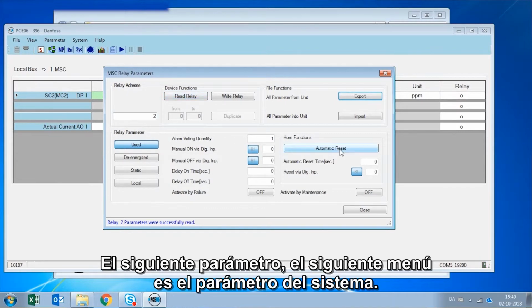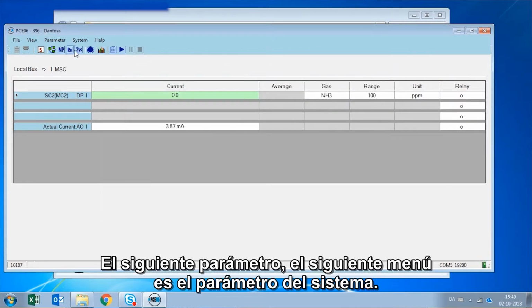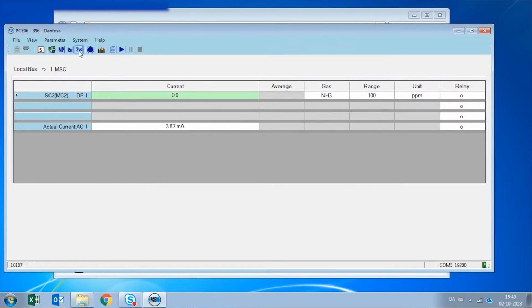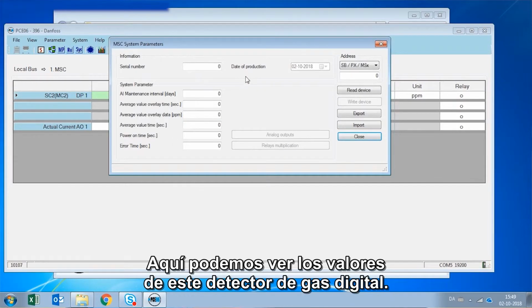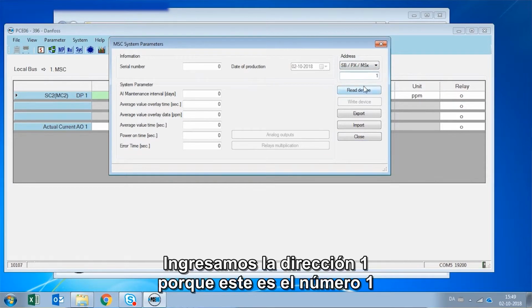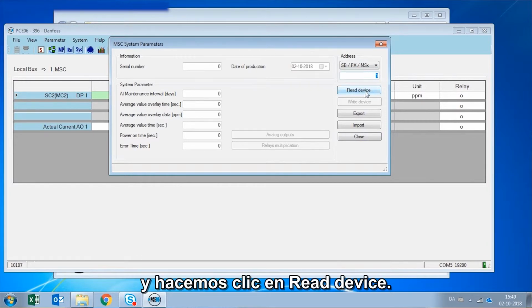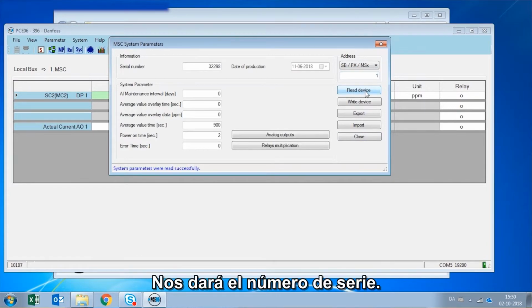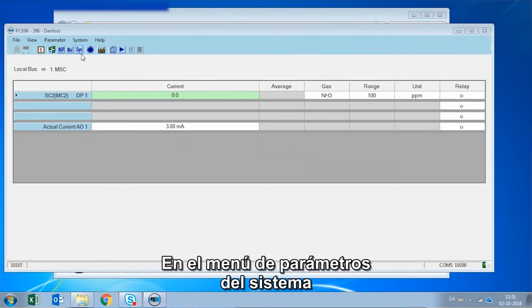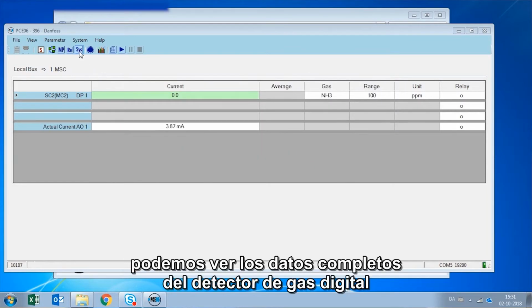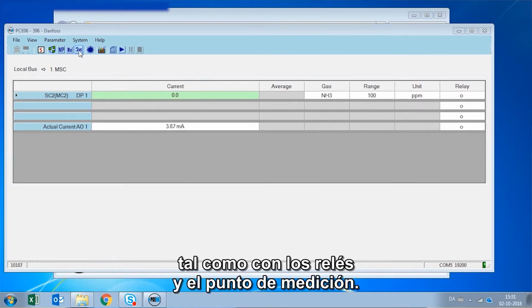The next parameter, the next menu is the system parameter. Here we can see the values of this digital gas detector. So we enter the address 1 because this is number 1 and we click read device. It's going to give us the serial number. On the system parameters menu, we can see the details of the complete digital gas detector, the same way we have seen with the relays and the measuring point.